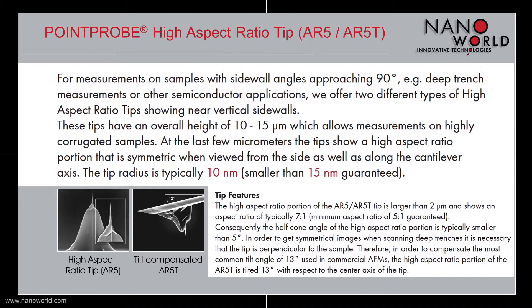The tips are between 10 and 15 µm high, where the last few µm of the tip have a high aspect ratio which is typically 7 to 1. This high aspect ratio portion is symmetric when viewed from the side as well as along the cantilever axis. The typical radius of our Pointprobe High Aspect Ratio Tips is below 10 nm, and a tip radius smaller than 15 nm is guaranteed.